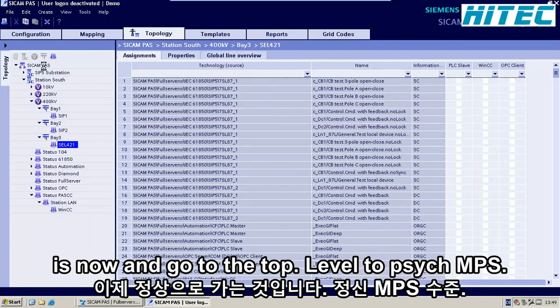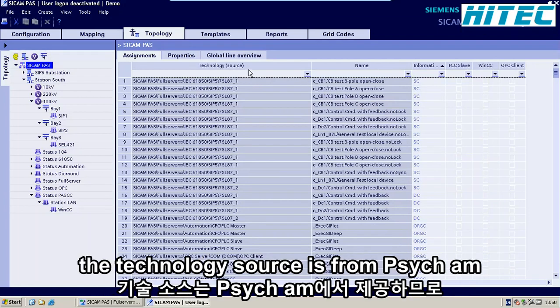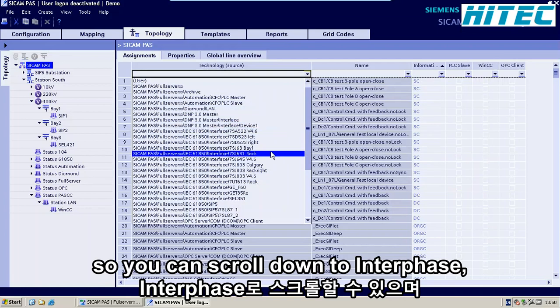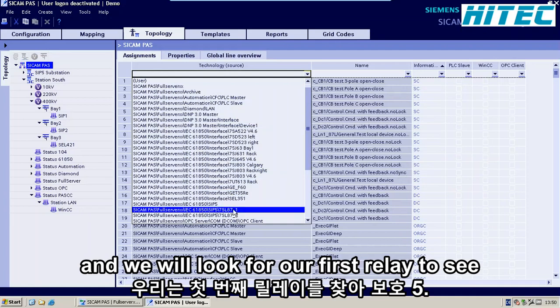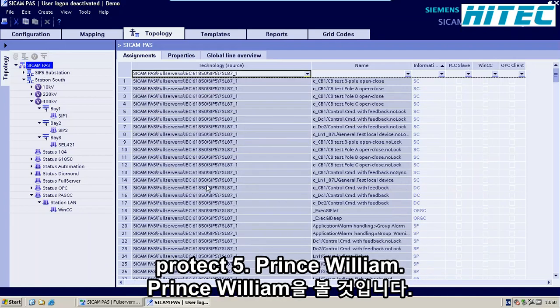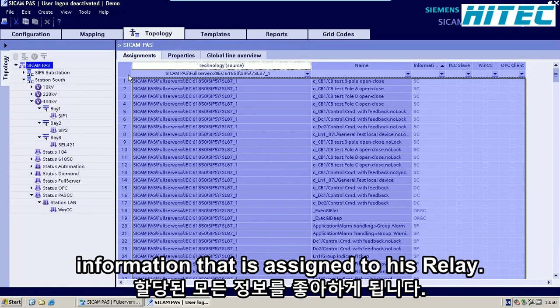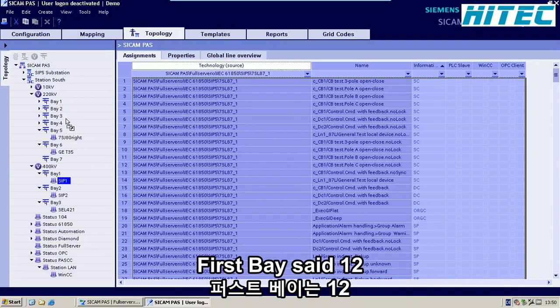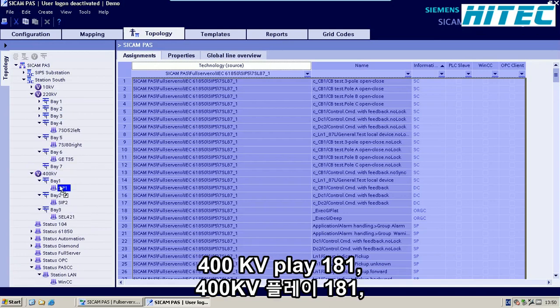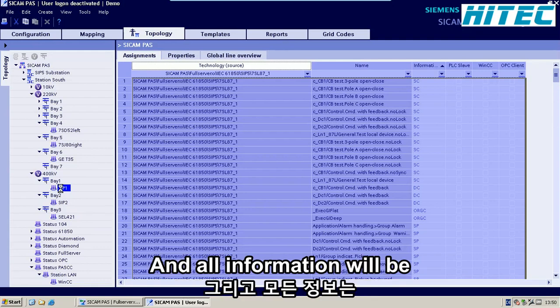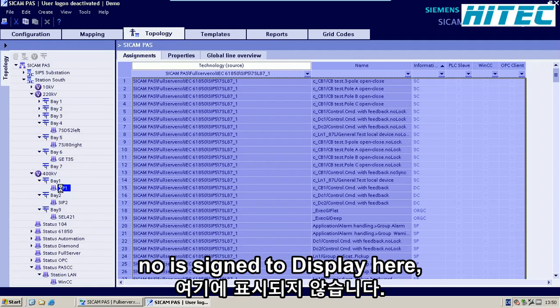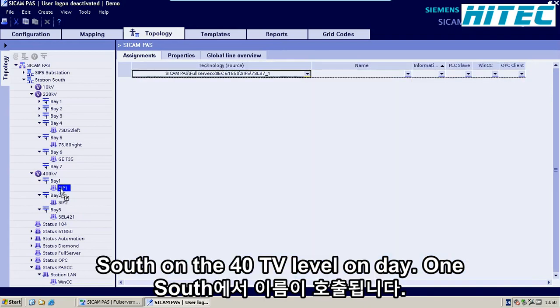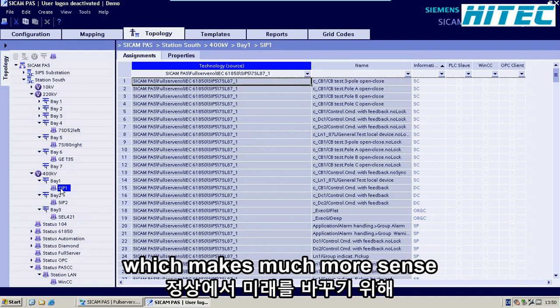We go to the top levels of SICAM PAS. The topology source is from SICAM, so scroll down to the 61850 interface and look for our first relay — the SIPROTEC 5 first relay. Click in that area to select all information assigned to that relay. Then hold the mouse and drag and drop it to our first bay: SIP 1 — 400 kV, Bay 1, SIP 1. Release the mouse and all information is now assigned to this bay. This means if the status changes, it will come up with a name like 'Substation South, 400 kV level, Bay 1, status of disconnect switch has changed,' which makes much more sense.